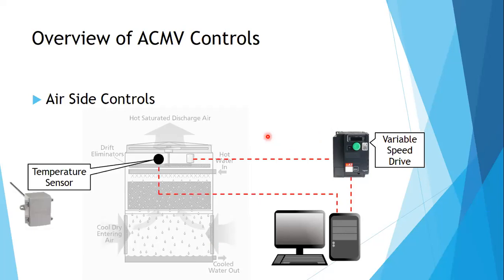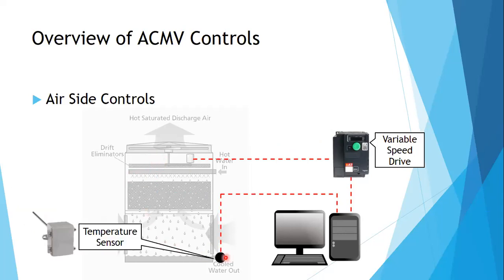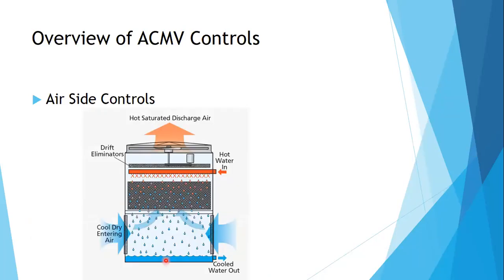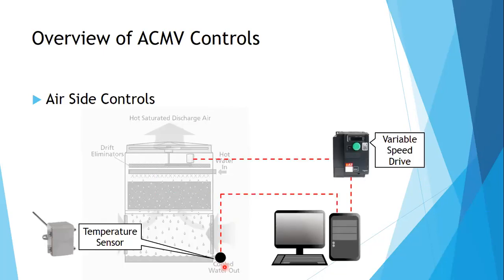For cooling towers, there's another option. Instead of measuring the temperature for your outgoing air, you can also measure the temperature of your outgoing water. You can see here, hot water goes in. You can monitor your cold water out. If for example, your set point for cold water is 26, and the actual condition is lower than your set point, then your variable speed drive can lower down. If it's higher than your set point, your variable speed drive can go up.